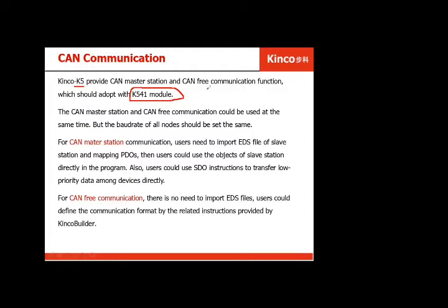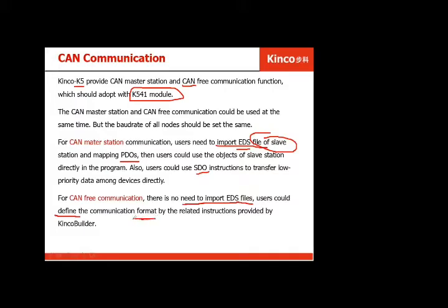For CANopen communication, we need to import an EDS file from the slave device. The EDS file contains PDO and SDO definitions. For free CAN communication, there is no need to import the EDS file, but you need to define the format using instructions.